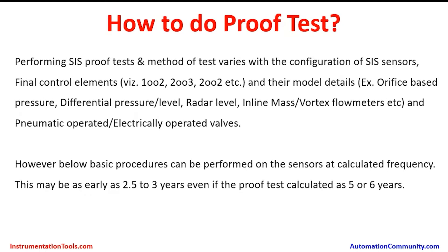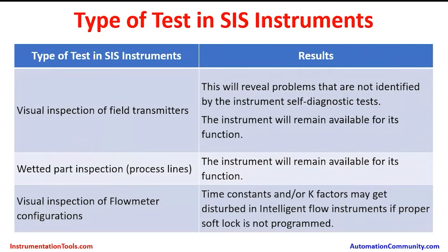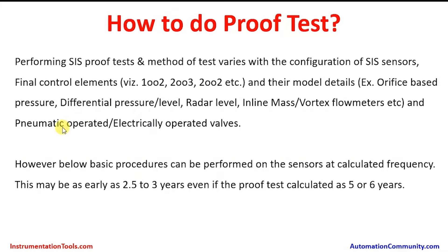Performing SIS proof tests — the method of test varies with the configuration of SIS sensors and final control elements, such as 1 out of 2, 2 out of 3, 2 out of 2, etc., and their model details — for example, Orifice based pressure, differential pressure level, radar level, inline mass flow meters, vortex flow meters, and pneumatically operated valves. For each type of instrument and valve, the testing may be slightly different and will also vary based on the type of configuration.